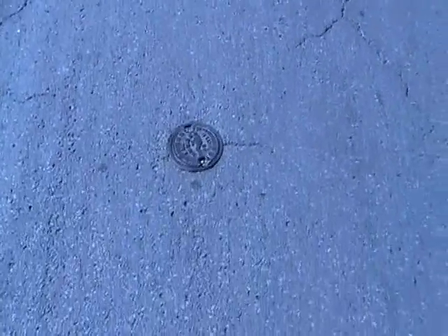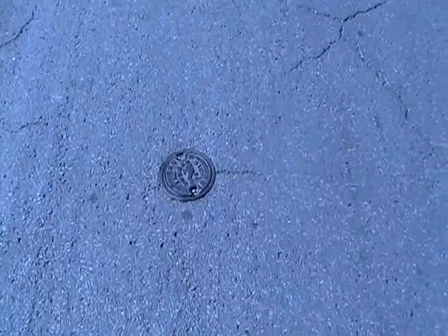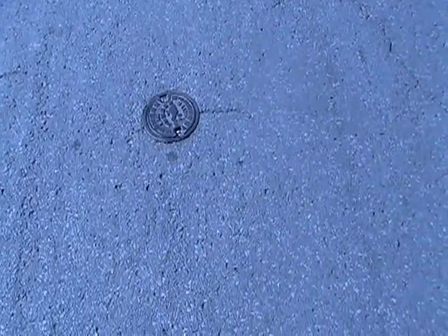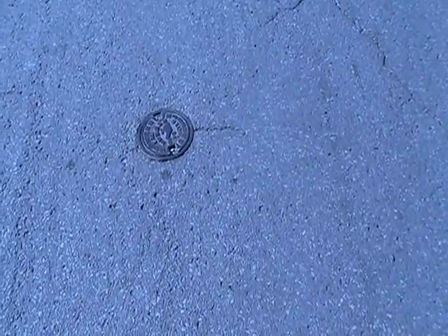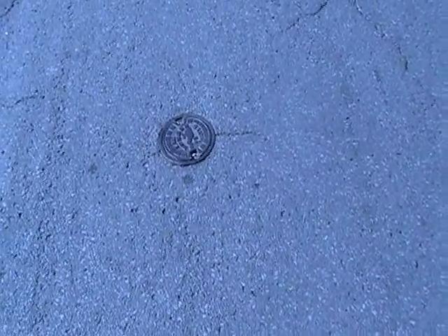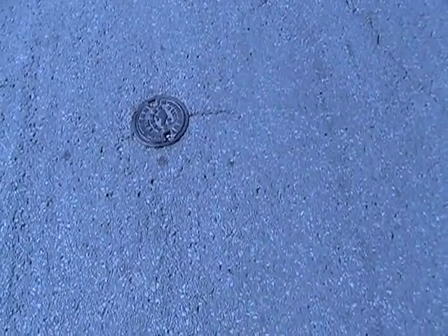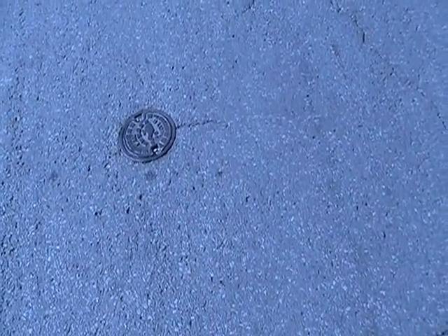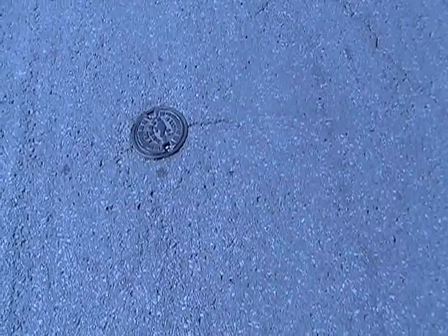The other network is the water main network, and clues you can see are these valves. Actually, these aren't the valves, these are accesses to the valves, but essentially this is like a tube with a little cover. And the valve, this would be a butterfly valve, so essentially at the top of the valve there's a nut, and if you want to shut the valve, you remove the lid and you have a tool which is a key. It looks like a capital T, and the cross portion stays out. That's what you need to turn it. You stick it down, you insert it into the nut, and then you can turn the valve and shut it that way.